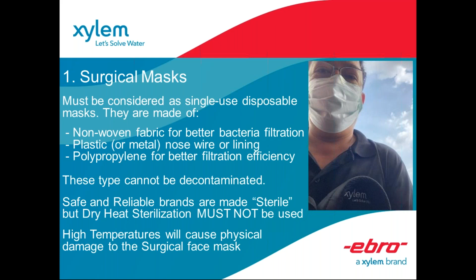So, how do the suppliers and manufacturers of these face masks make it safer for us? By ethylene oxide sterilization. Ethylene oxide is a gas, an explosive gas, and it undergoes four phases. That's preconditioning or conditioning, exposure, which is sterilization, exhausting for post conditioning, and purge, which is pulling the vacuum out of the chamber. And this takes many hours to complete.